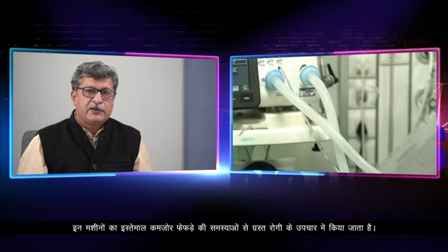The Indian Standard 80601 Part 2 Section 12 establishes the basic safety and essential performance requirements of a ventilator and its accessories in terms of oxygen level alarm conditions and alarm for airway pressure, expired volume, electrical supply failure, gas supply failure, etc. For the purpose of testing, this standard prescribes gas flow rate and leakage specifications of the ventilator. It also mentions the cleaning and disinfection of the equipment.